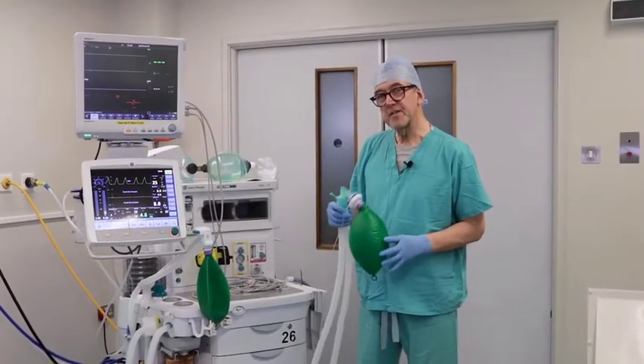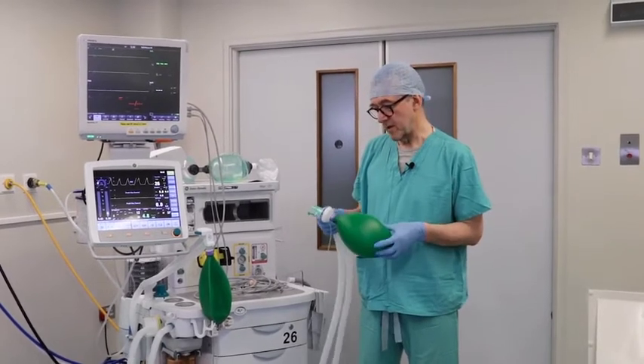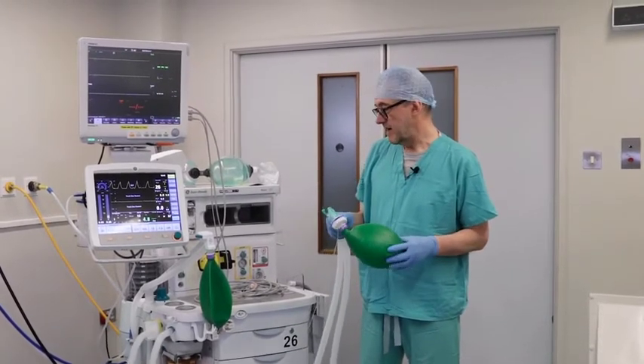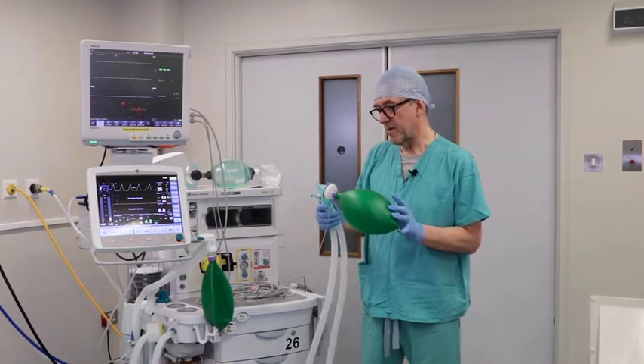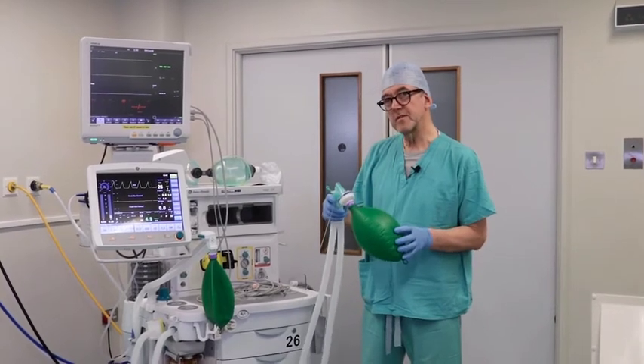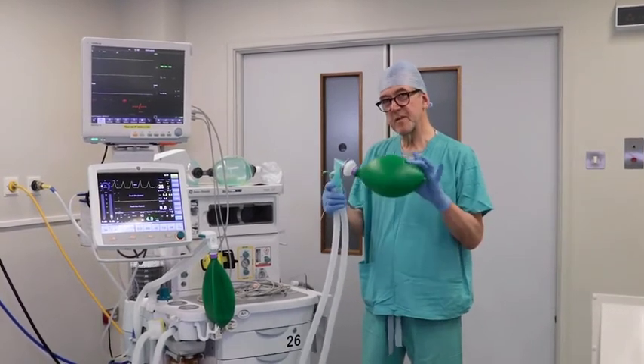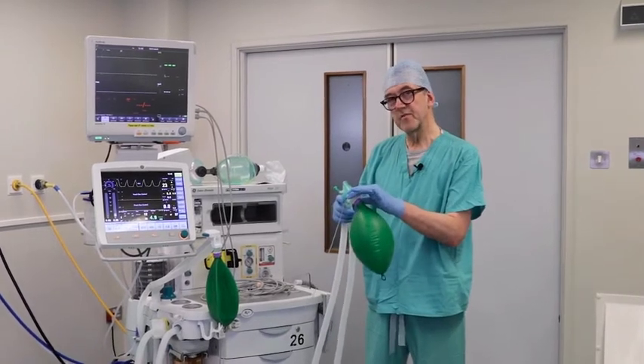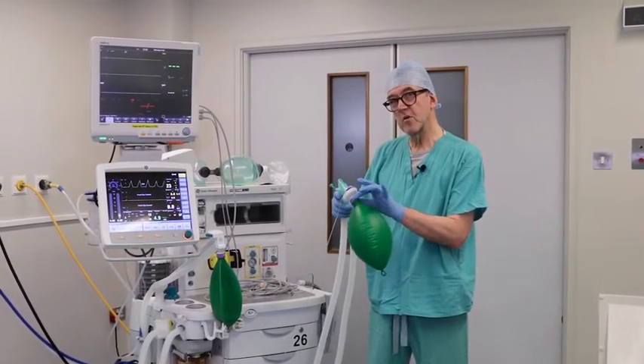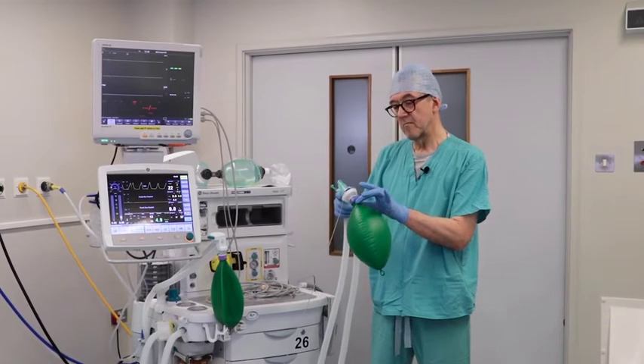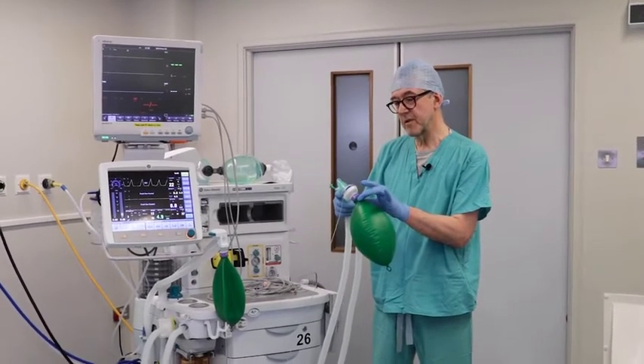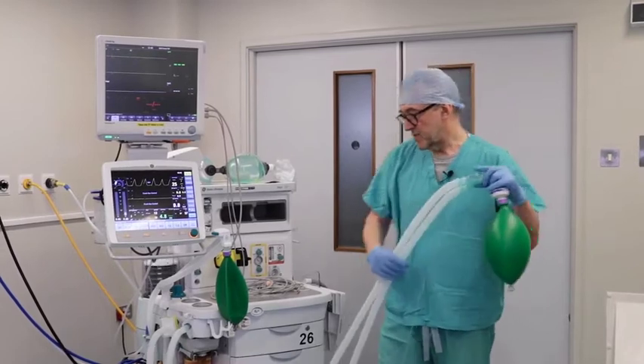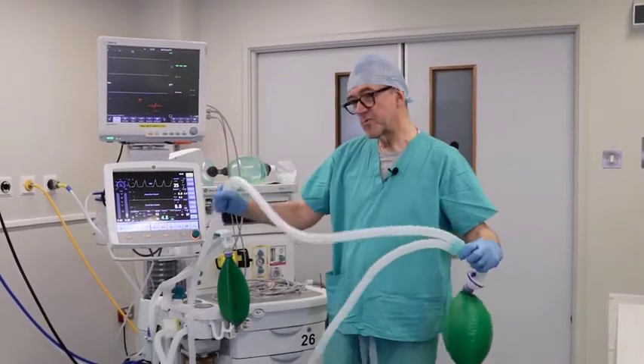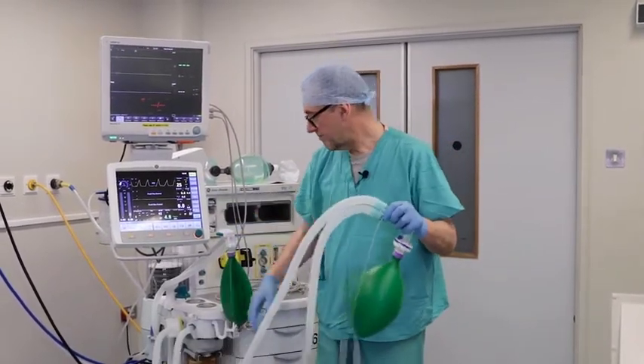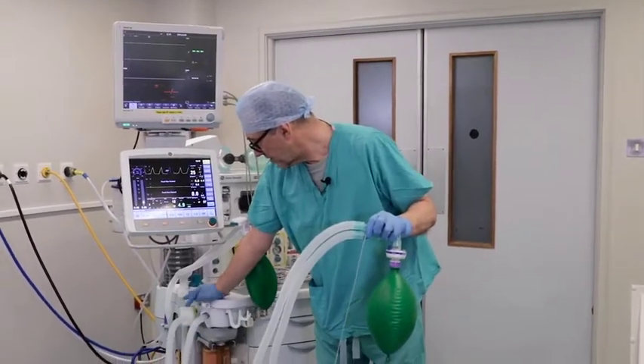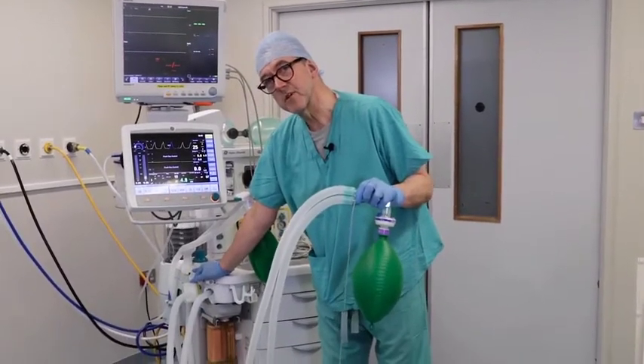So the ventilator is currently set up to run automatically as a ventilator, and we're currently ventilating this reservoir bag. So I'll go through the breathing system from the bag, which represents the patient. Then there's a filter. There would be your closed suction before the filter, which I think has been discussed already. And this is the breathing system. It's got an inspiratory limb and an expiratory limb. Going back to the machine, on the expiratory limb there's a second filter.